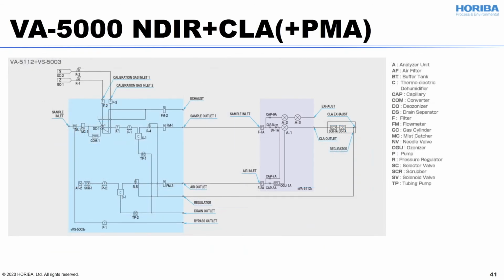And this is another sampling gas system with the chemiluminescence analyzer, NDIR analyzer, and the PMA analyzer. Here's a drain separator to knock out the moisture, going through the mist catcher. Here is one line and another line going through a NOx converter, because the orange line is showing the raw NO line and the pink line is the NOx line, because the NOx converter converts NO2 to NO, so you can measure the total NOx.